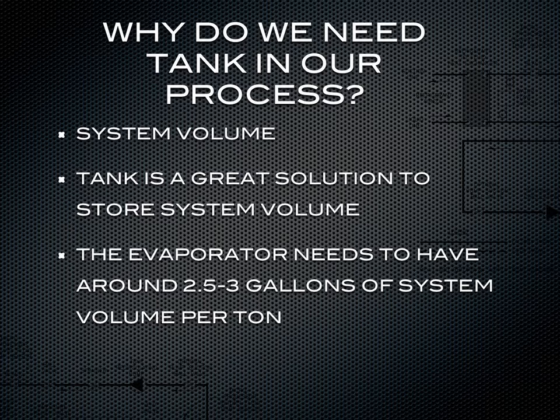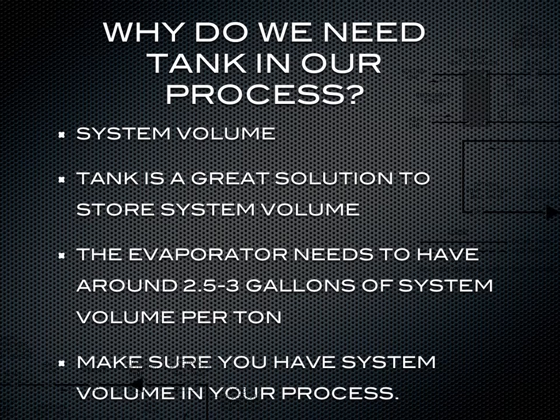For example, if you have a 5-ton chiller, there needs to be around 15 gallons of system volume. A 30-ton chiller will need around 90 gallons of system volume. If you don't have enough system volume in your process, you're basically going to short cycle your compressor, shut down your refrigeration system, and the piece of equipment is not going to get cooled.